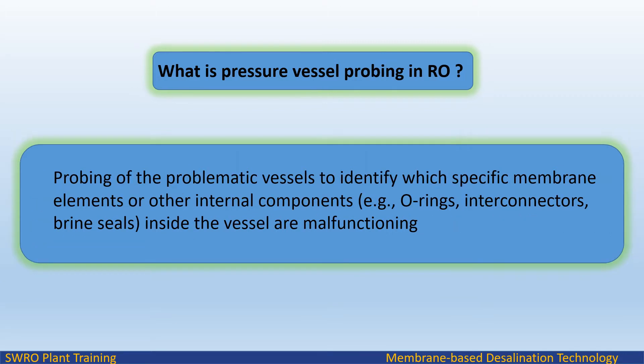What is pressure vessel probing in RO? Probing of the problematic vessels identifies which specific membrane elements or other internal components — such as O-rings, interconnectors, and brine seals — inside the vessel are malfunctioning.